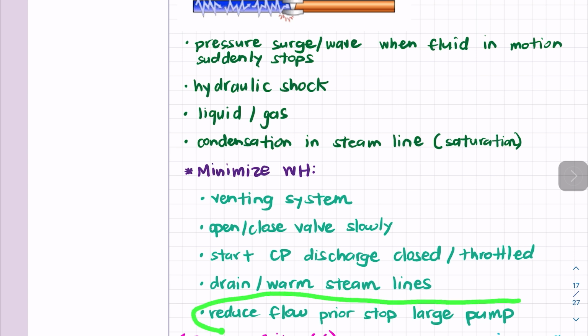Also, reducing the flow prior to stopping a large pump is important to minimize water hammer. Another way to prevent it is by installing devices such as air chambers, since they provide a cushion of air to absorb the shock wave, or pressure relief valves.